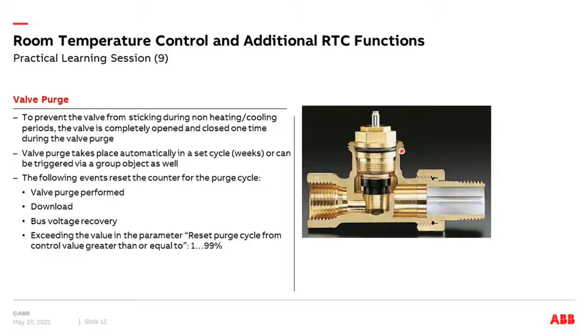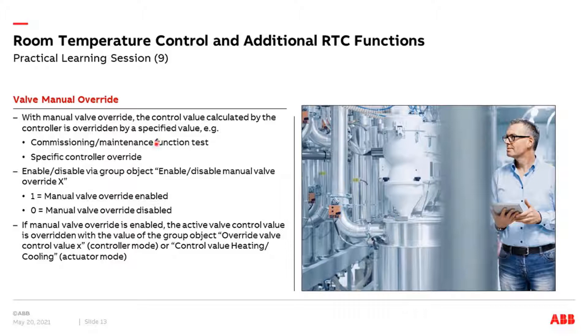Via KNX telegram we can override the calculated control value — for example for commissioning, maintenance, or tests. It is possible to override the calculated value using a one-bit information to activate it, and then via one byte send the manual override value. Then you will see the fan and also the valve follow exactly this manual value.